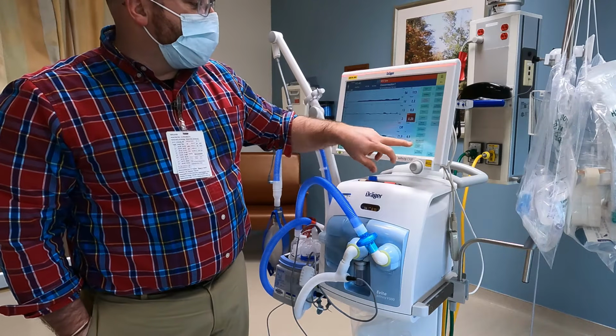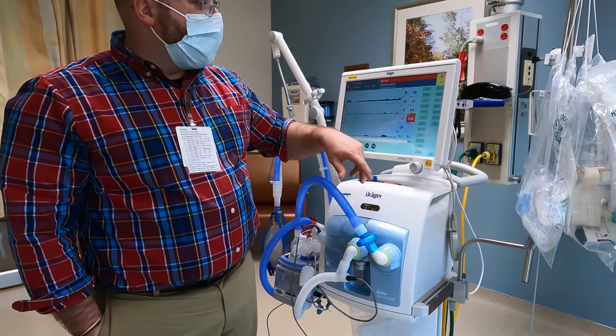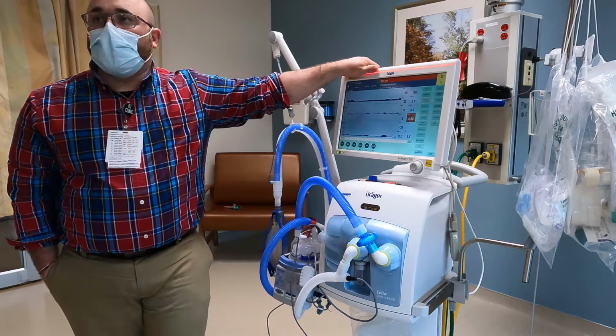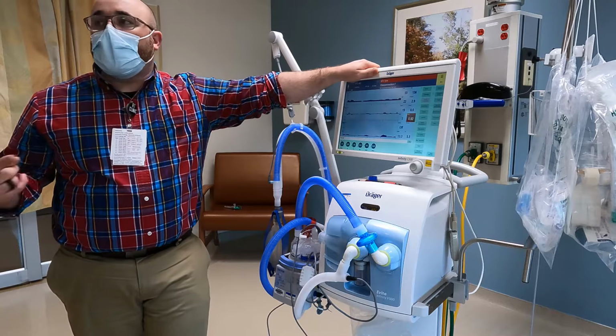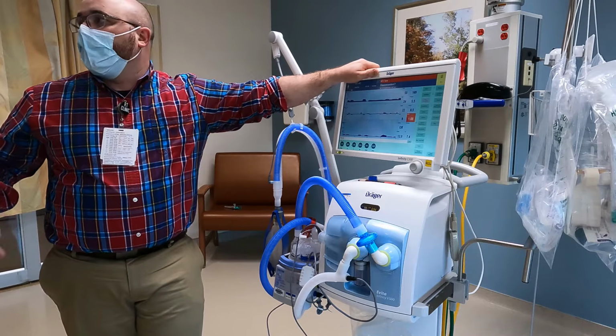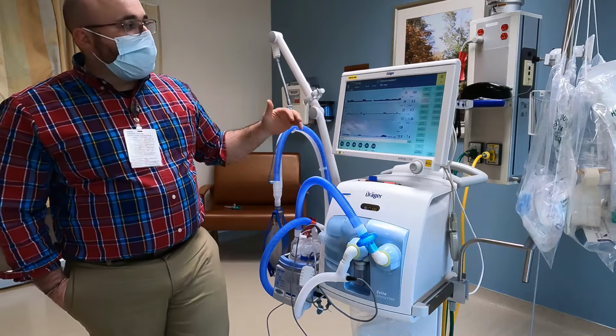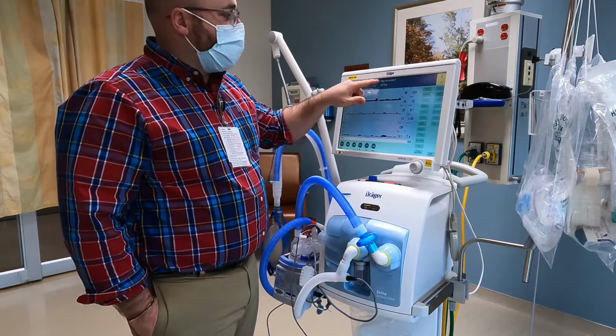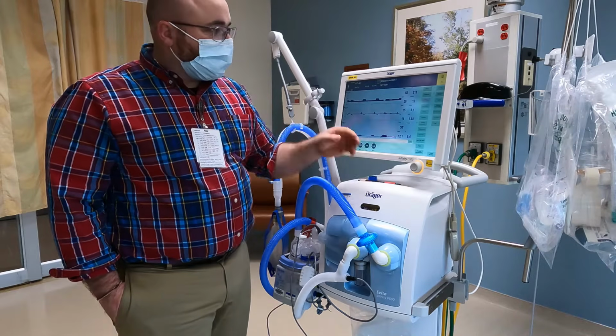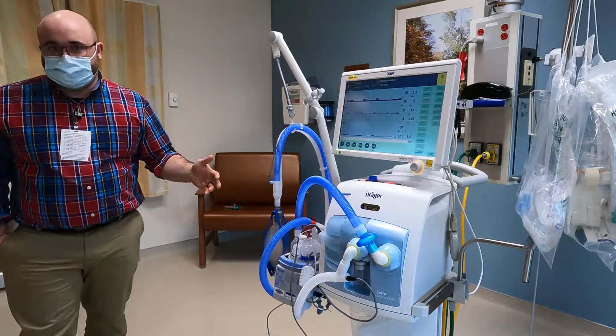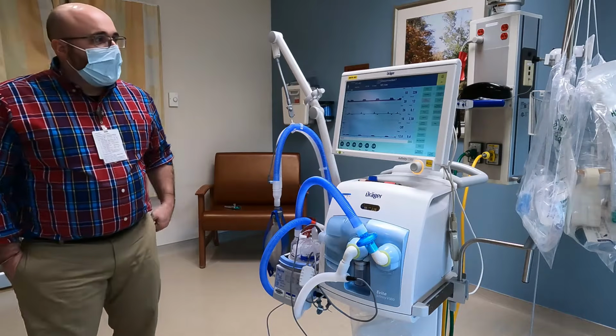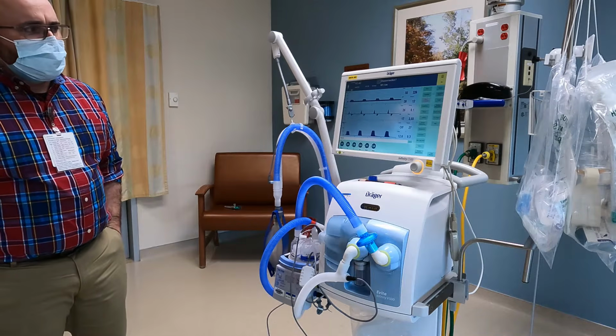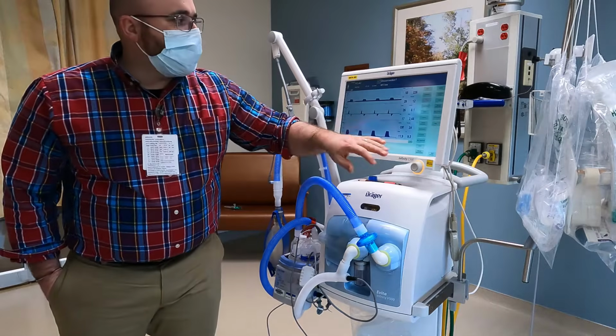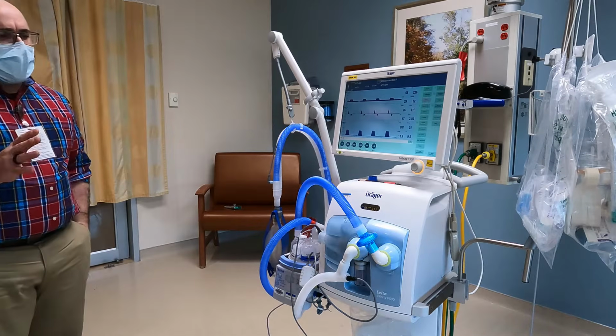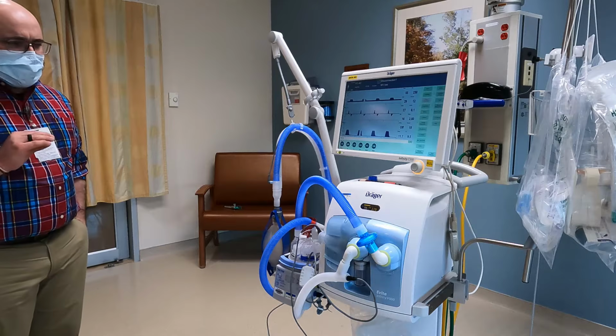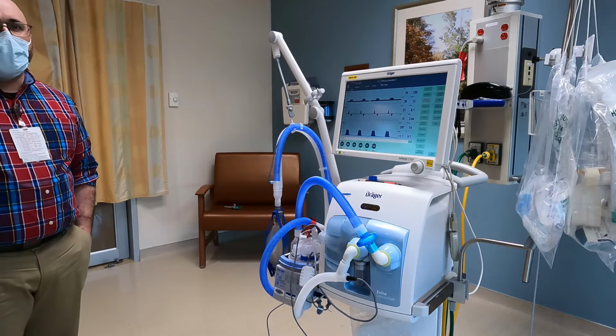Now here's an interesting thing. So when I silence that, it does leave it silenced for a long time. If a different type of alarm happens, it will alarm over it. So you're not silencing absolutely everything. It just does that specific alarm. So let's say you heard that alarm. You came in here and now you're like, okay, there's no alarms right now. Say that's shut off. You came in, there's no alarms right now. Everything seems to be attached. What was the deal? Why was it red alarming?